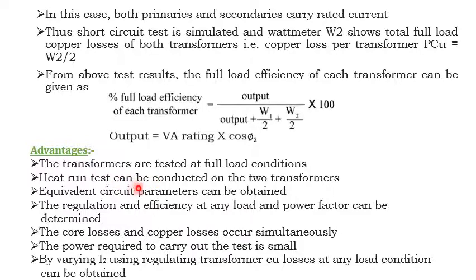So that is, heat run test can be conducted on the two transformers. Then one more advantage is that the equivalent circuit parameters can be obtained. So the equivalent parameters can also be obtained by the OC/SC test, and this test is also helpful for obtaining the equivalent circuit parameters of the transformers. The regulation and efficiency at any load and power factor can be determined from this test.